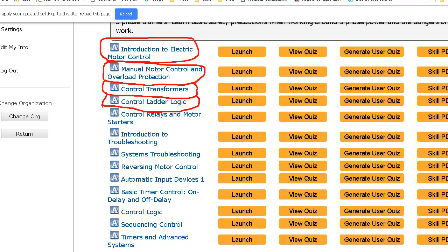One of the things we also need to remember, there's a question, and I know it was in there, but the NEC requires that if you have a voltage above 50 volts AC, we need to bond that neutral to ground. Remember, we've been doing that in the labs. Remember how transformers are rated. They're not rated in watts or amps. They're rated in volt amperes because of the fact that that rating applies to both the primary and secondary side.